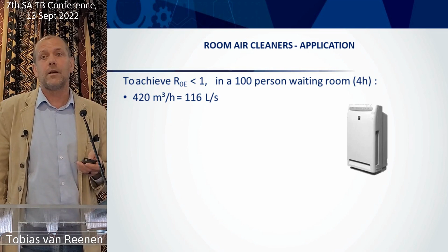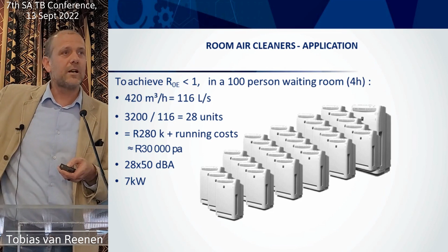A system like that with 28 of those guys is going to cost you nearly 300,000 Rand, excluding running costs, which would be about 30,000 Rand per annum. And they're noisy. This is going to run at 50 dBA each, 28 times 50 dBA. I can't do the math. It's logarithmic acoustics stuff. Call my wife in. I don't know how to do that. It's a lot of noise. You're not going to be able to hear yourself think in that room. And 7 kilowatts of power. Okay, so these kind of things don't help for congregate settings.